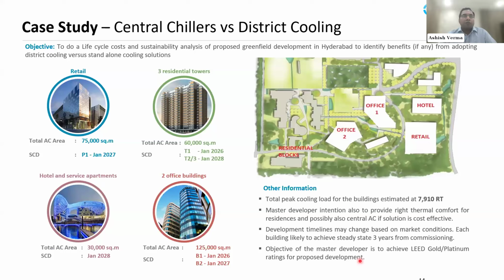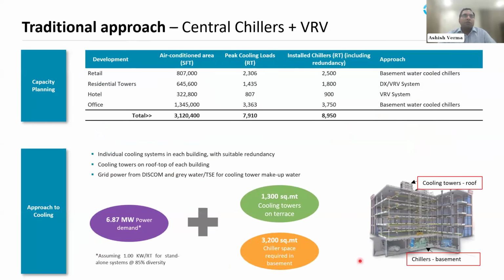Sure, thank you. So this is a case study on district cooling. It is a mixed use development where we have a combination of retail buildings, residential buildings, hotel service apartments, and office buildings. The estimated cooling load for this development was around 7,900 tons. The master developer also explored if central air conditioning could be provided for the residential blocks. So we have two approaches. First is the traditional approach, where we have individual cooling plants for individual buildings, whether central chillers or VRV. We considered chillers for the retail, VRV or DX system for the residential, VRV for the hotel, and chillers for the office space.